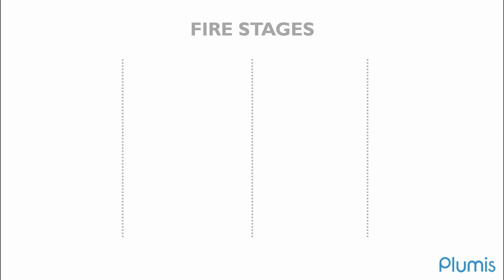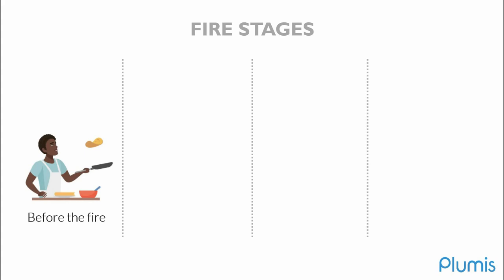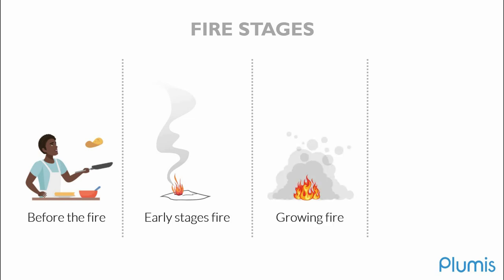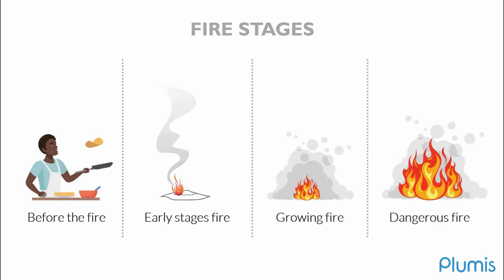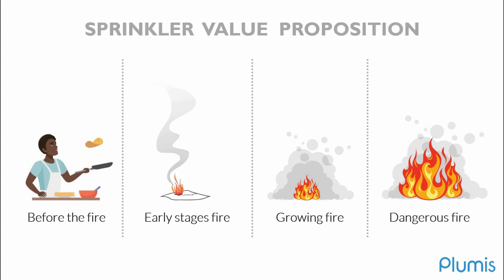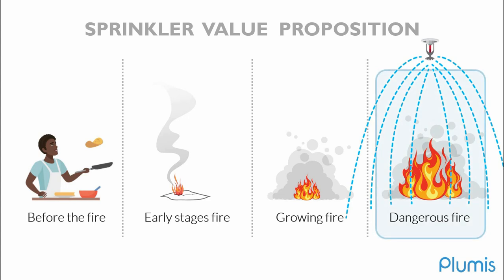Now, another reason why Automist is different is because we're looking to address multiple stages of the fire's development. So if we break it down into 4 pieces, we've got the stage before the fire, the activity that the occupant is doing. We've then got the early stages of the fire. We've got when the fire is growing, then finally when it becomes dangerous. A traditional sprinkler's proposition, where it provides value, is at this point, you need to build up a significant amount of heat to break that glass bulb, the actuator for the ceiling mounted system. Therefore, if you are close to the fire, you can also be at risk. So it waits till this later stage before they activate.